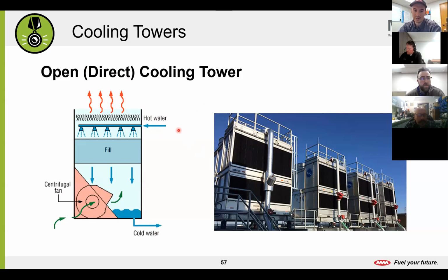What that means by open is that hot water coming from the space, let's say we were in a building with hydronic heat pumps and they're all running AC and all putting that heat from the space into the water. Well, we've got to reject that. So that hot water comes back from the building and then it literally dumps it over the top of this fill media here, where outside air passes through and we reject that heat outside. You'll typically see a lot of steam rising off the top of them. Downtown, you'll see that a lot. And then it falls down into the sump and returns back to the building.